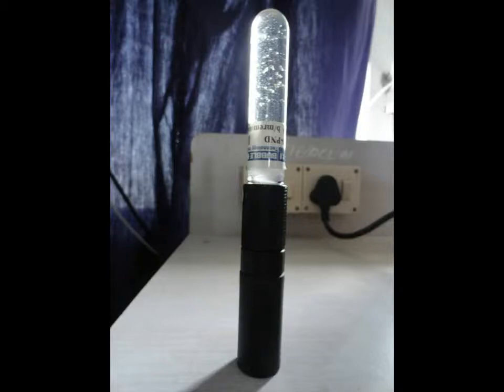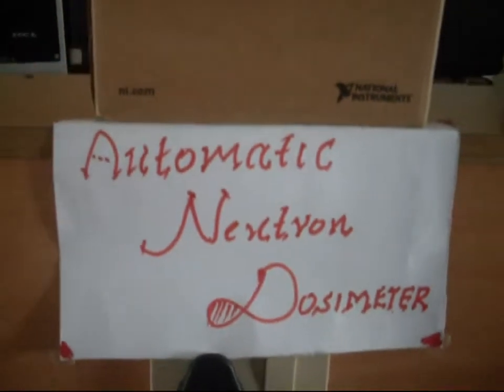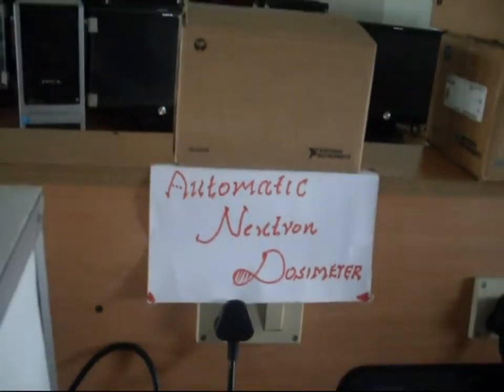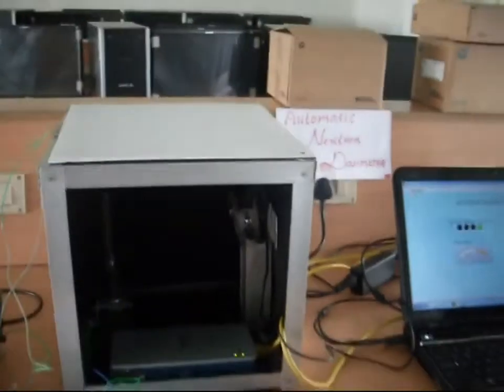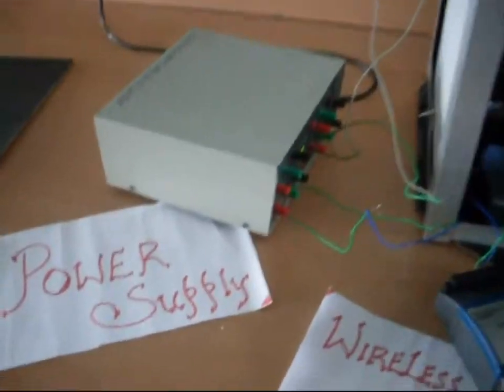Bubble detector is a neutron radiation sensor consists of a supercooled liquid that is dispersed over clear polymer. When a neutron strikes a polymer, it vaporizes and forms bubbles. Thus the number of bubbles formed is proportional to the neutron radiation dose.